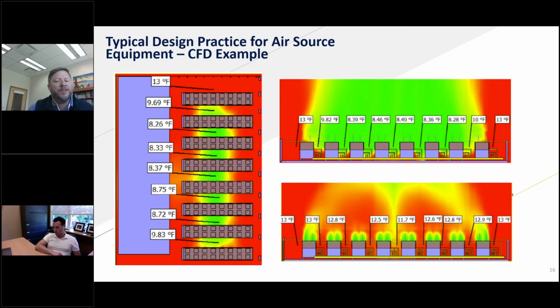And so what ends up happening is we get some of that, and some of that mixes with our discharge air that we're cooling down. And that's how you end up with approximately a 5-degree differential between the coldest air and the ambient. Okay, and so again, if we were to slide these units closer together, that differential would become larger. So if these units were closer together, meaning we have less free area to bring in fresh air from, that 8.26 degrees would be reduced, right? 13-degree ambient, if we put them closer together, you might be seeing 6 degrees or 4 degrees or 2 degrees.